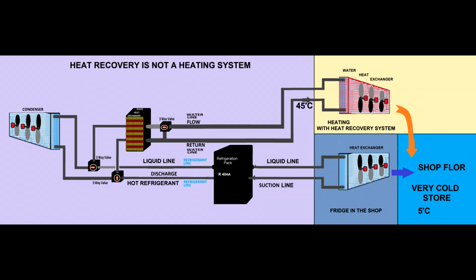And believe me or not, the heat recovery was heating the water as well, which was going down the drain. It's a little bit complicated. So what you'll see in this picture is very easy. The refrigeration equipment will take the energy from the store, and instead of dumping it outside via the condenser, we'll circulate the refrigerant through the plate heat exchanger, and then normally the water which circulates through that plate heat exchanger will take that energy and bring it back into the store via the heat exchanger.